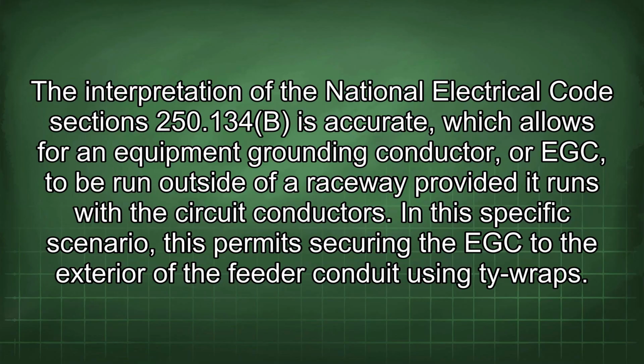The interpretation of the National Electrical Code sections 250.134(B) is accurate, which allows for an equipment grounding conductor, or EGC, to be run outside of a raceway, provided it runs with the circuit conductors. In this specific scenario, this permits securing the EGC to the exterior of the feeder conduit using tie wraps.